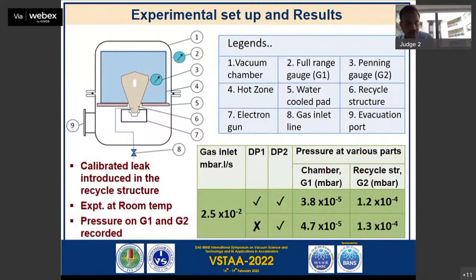And there is a calibrated leak that has been put inside. Our purpose is to check the pressure on these two gauges. What is the difference? Ideally, they should be the same. Whether there is a difference or not, at different leak rates. We have done this for 5 or 6 leak rates. I have just provided one in the green part below.